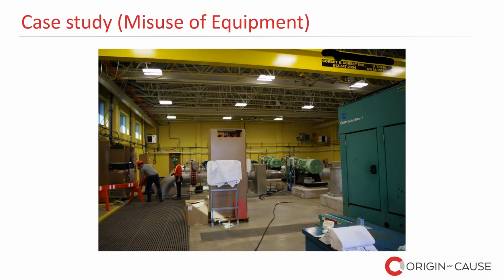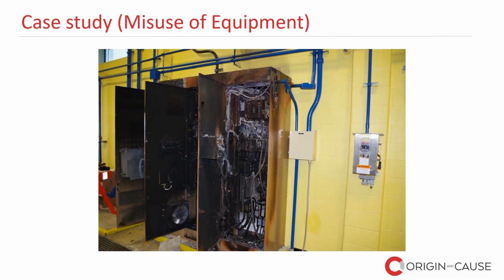For the next 2 case studies, we'll be touching upon misuse of equipment. This first case study involved a failure of an 11-year-old variable frequency drive, or VFD, in a water pumping station. A variable frequency drive is used to control alternating current motor speed and torque. Collected information determined that this pumping station was not the main pumping station. In the 2 months prior to the fire, the pumping station had been utilized more frequently. At the time of the fire, the VFD was under a load greater than it was typically called for, and the main breaker had tripped.